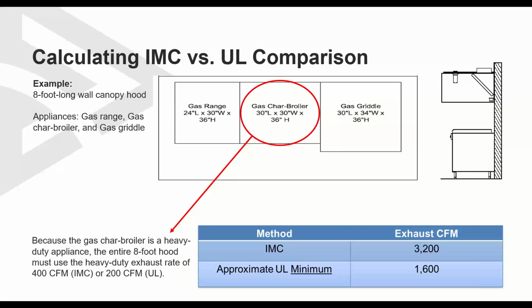Doing a simple calculation to compare IMC versus UL, this example here is an 8-foot long wall canopy with an appliance of a gas range, charbroiler, and griddle. The note I have here says because the gas charbroiler is a heavy-duty appliance, the entire 8-foot hood must use the heavy-duty exhaust rate of 400 CFM per IMC or 200 CFM per UL. And again, that is per lineal foot. Translating that, you would take your 400 times 8, and you would get these exhaust CFM rates, depending on IMC or UL. Notice how I underlined minimum. These are the minimum exhaust rates. That doesn't technically mean that it's recommended.